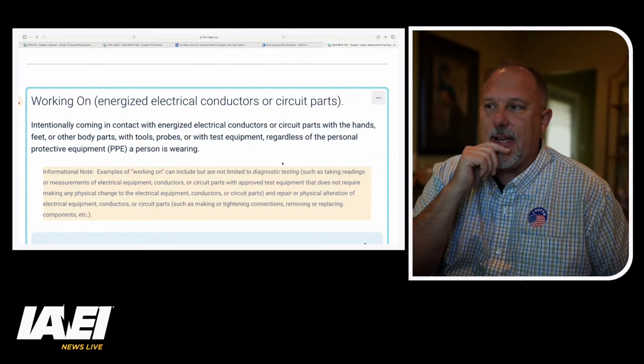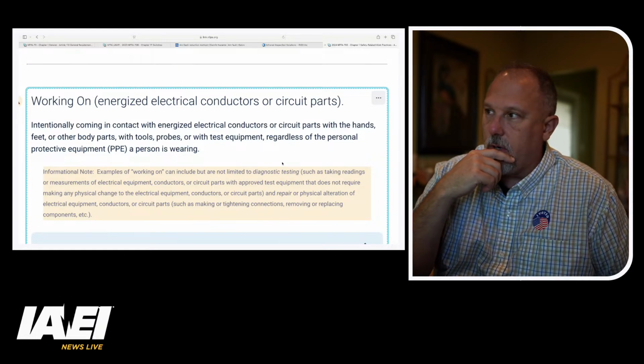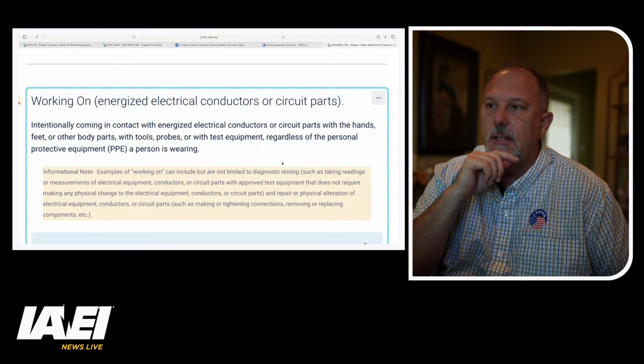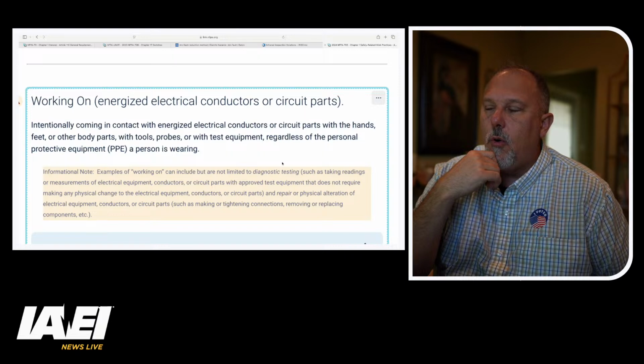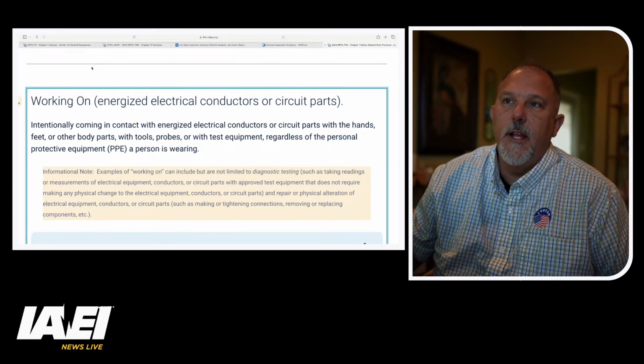So let's talk about what is work. That's another point of discussion. If you think about 70E, I'm going to go back over to the NFPA link. When you think about 70E, what is work? I don't think, like, working on. Let's see if it's a defined term. Let's go to W's. There's not working distance. Working on is a defined term. Let's take a look at the definition of working on. It says intentionally coming in contact with energized electrical conductors or circuit parts with the hands, feet, or other body parts, intentionally, not by mistake, with tools, probes, or with test equipment, regardless of the personal protective equipment the person is wearing.